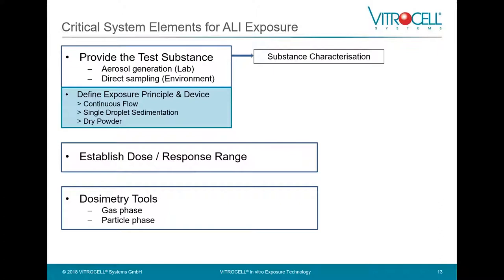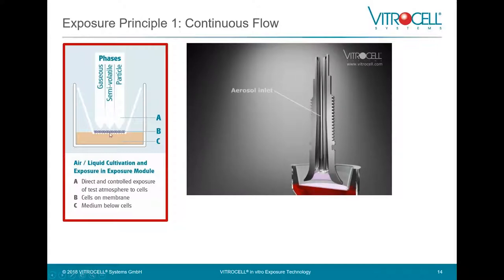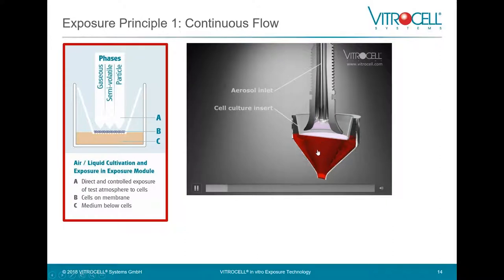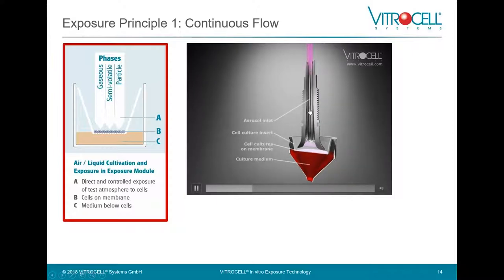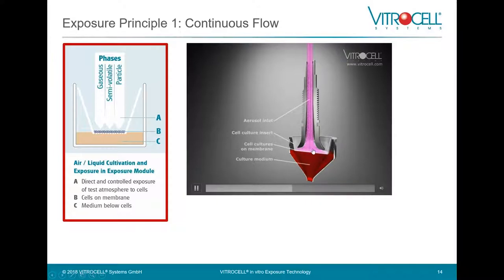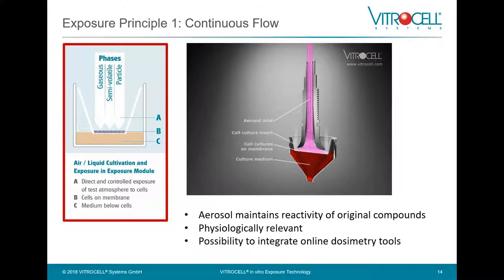Now let us define the exposure principle and device. We have three exposure principles: continuous flow, single droplet sedimentation, and dry powder. The continuous flow principle at the air-liquid interface works by guiding the aerosol through an inlet at a low flow rate ranging from 2 to 100 milliliters per minute in a continuous manner to the cells on the membrane. The advantage is that the aerosol maintains the reactivity of the original compounds, it is physiologically relevant, and it is possible to integrate online dosimetry tools.